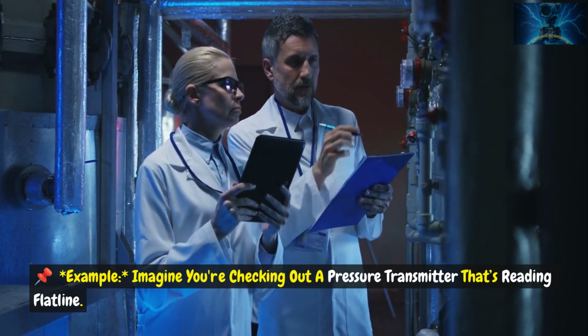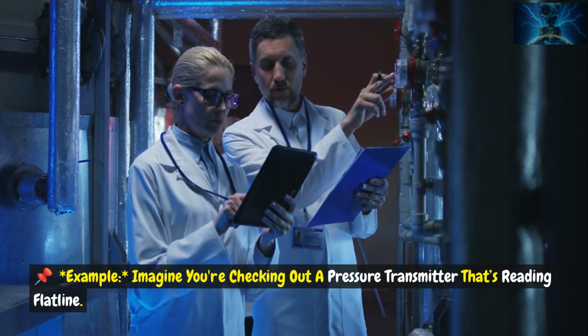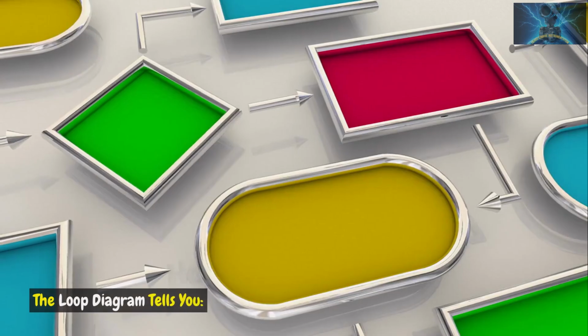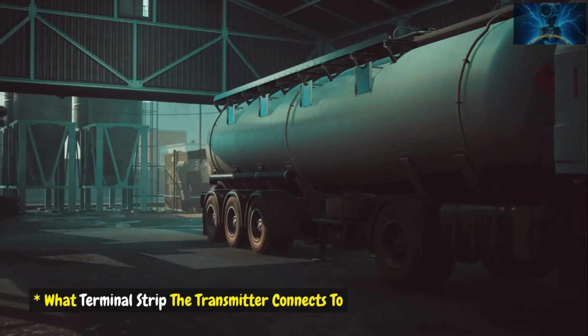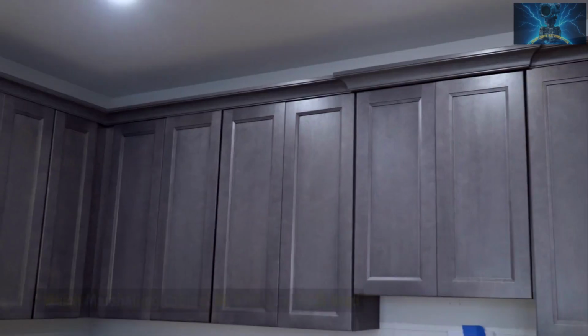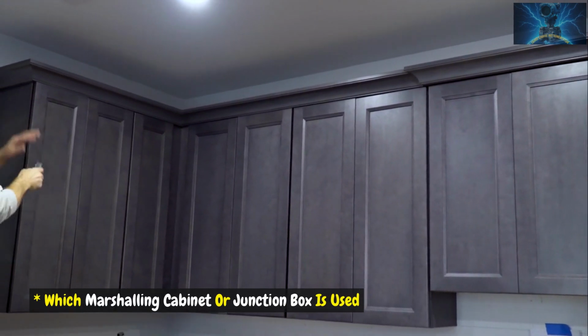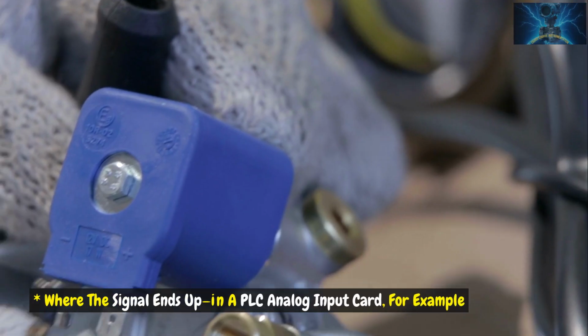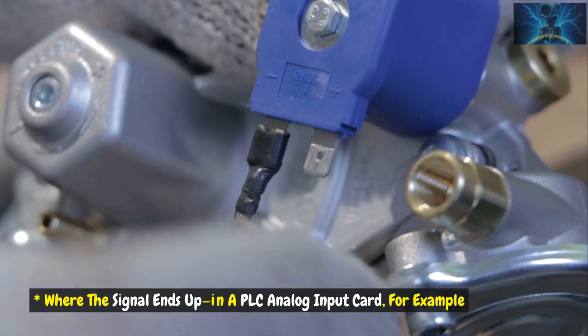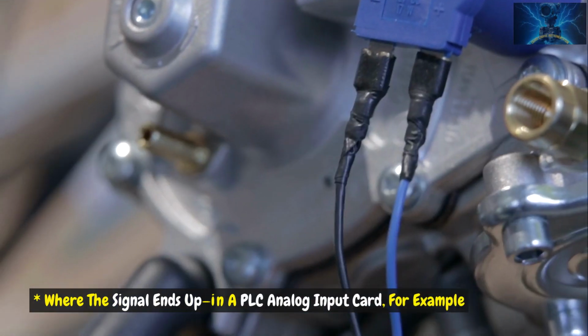Example: imagine you're checking out a pressure transmitter that's reading flatline. The loop diagram tells you what terminal strip the transmitter connects to, which marshalling cabinet or junction box is used, the wire color or number, and where the signal ends up, in a PLC analog input card, for example.